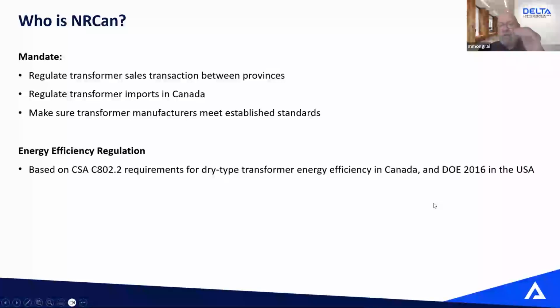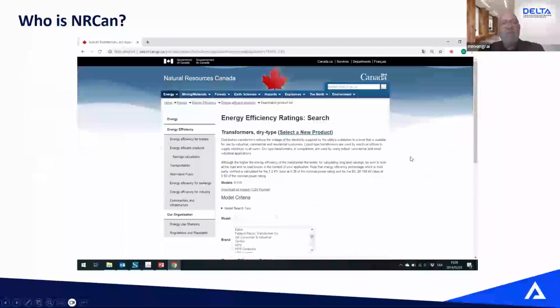It's going to be, again, a major increase in efficiency, increase in transformer costs, increase in transformer dimensions. So we don't know yet exactly where it's going to go, because at first the intention of increasing the minimal efficiency was so high that it would have prevented all manufacturers from using the current material, the current core steel and everything. We would have to jump to amorphous steel. There's not enough capacity in the world to do so. So now there's lots of pushback in the industry on the American government to bring those efficiency levels to a point where we can still use material that there's enough volume of in North America so that every manufacturer can have access to those materials. So it's going to come. It's probably in 2-3 years from now that we're going to have to deal with this next efficiency change.